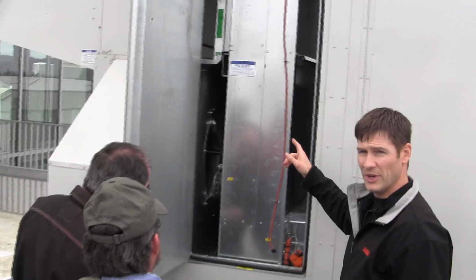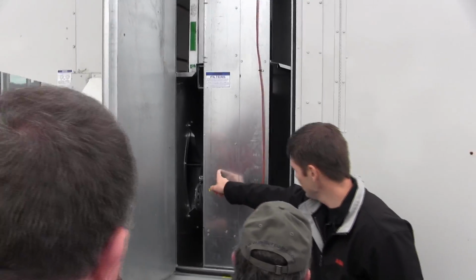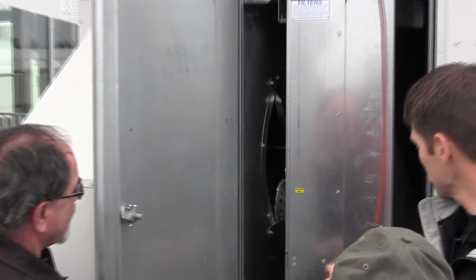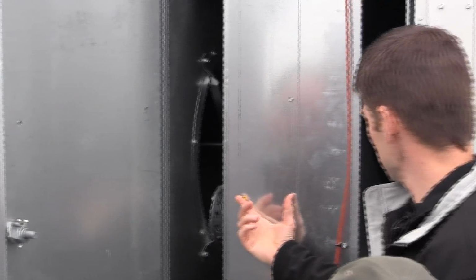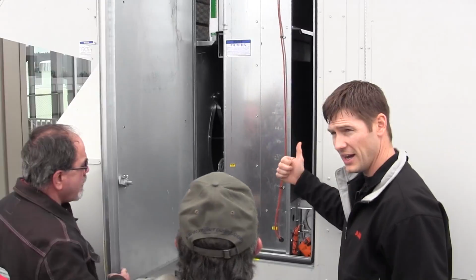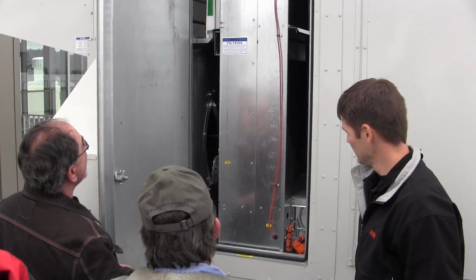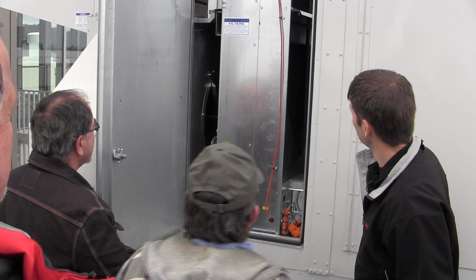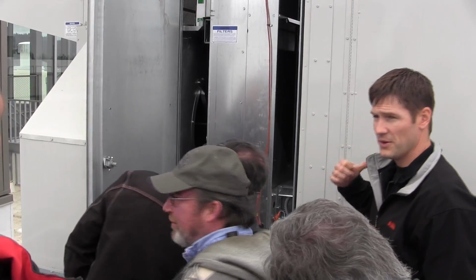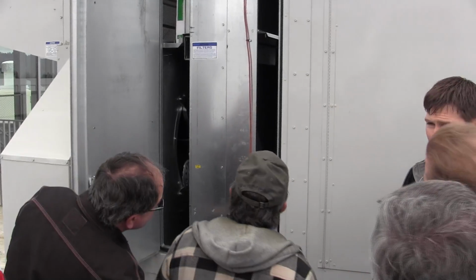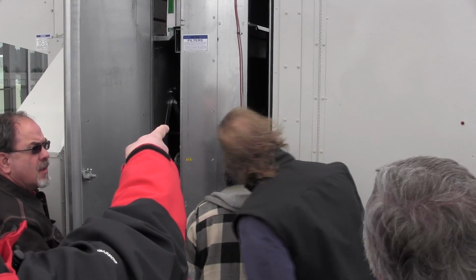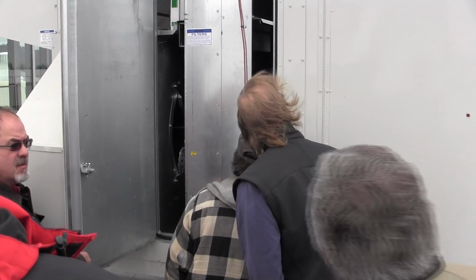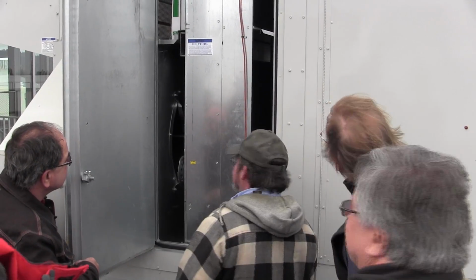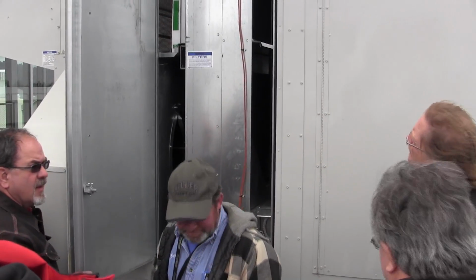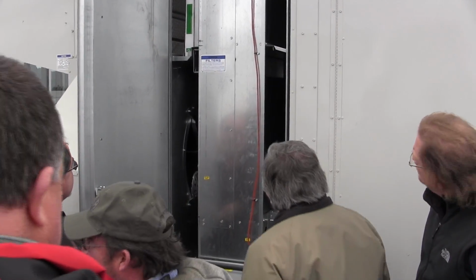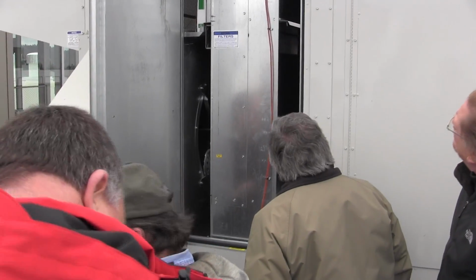So there's actually a double wheel in here. There's one wheel here and one wheel here. If you took this panel off, you should be able to slide this one out. There's a door on the other side to slide the other one out the other way. Oh, I can see it doesn't move very fast, does it? Right. And we could turn it off if you wanted, but there you can see the pie pieces. You kind of see right through the screen right there. It's not moving very fast. No, it's not. I think each one has its own motor. Faster than one over in building 30.